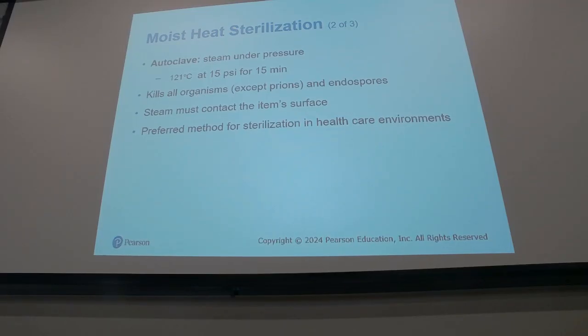So for the autoclave, we have specific parameters that you have to follow. No matter that you might have a thermal death point of 10 minutes, in these autoclave machines, we have a minimal temperature of 121 degrees Celsius.